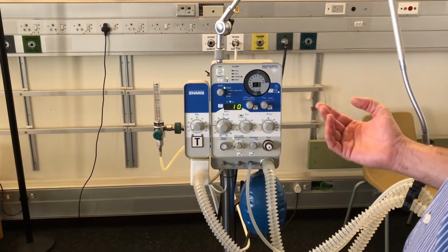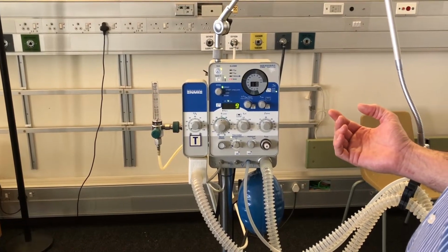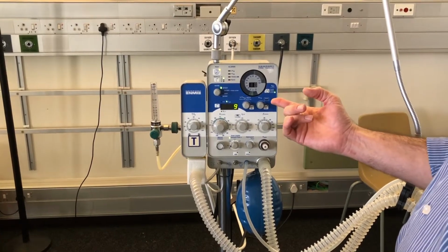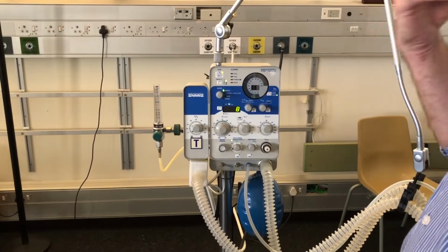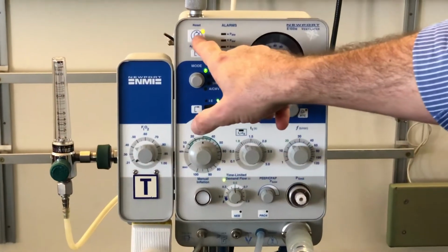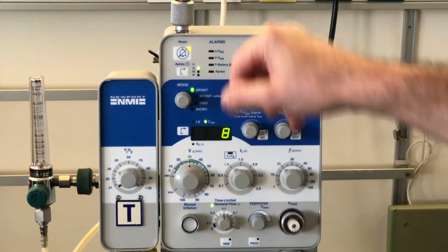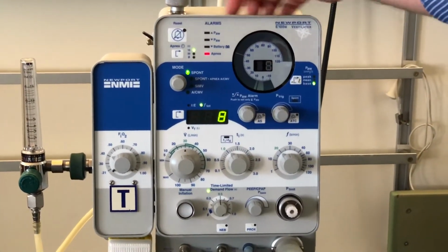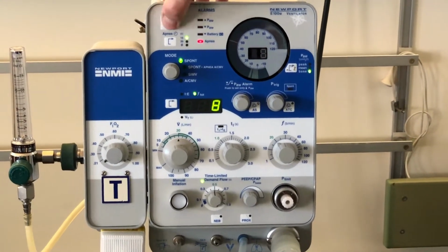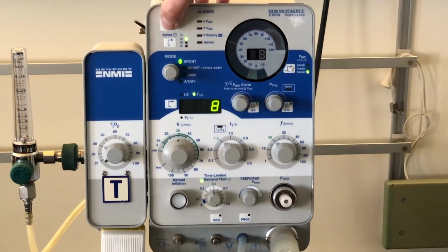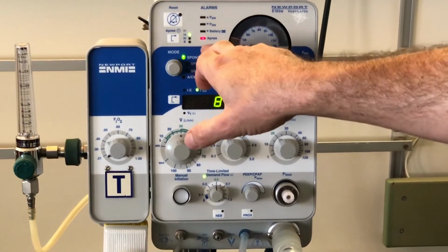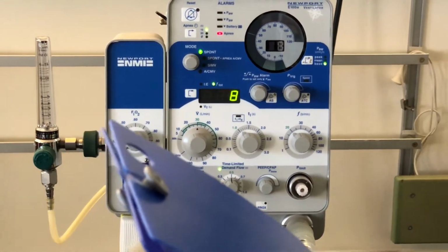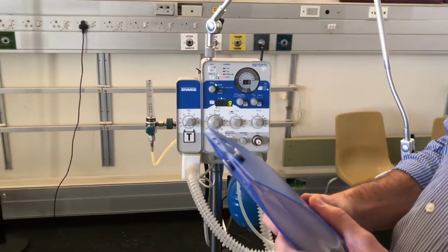Okay, we should be close to 15 seconds now. There you go, the light starts to flash again. The reason you're not hearing the alarm is the alarm is still silenced from the last time that I pushed it. There you go, you can hear the alarm. Again, it doesn't matter how many times I push the alarm reset button, I can't stop the machine from flashing the apnea alarm. The patient has to commence respiration.